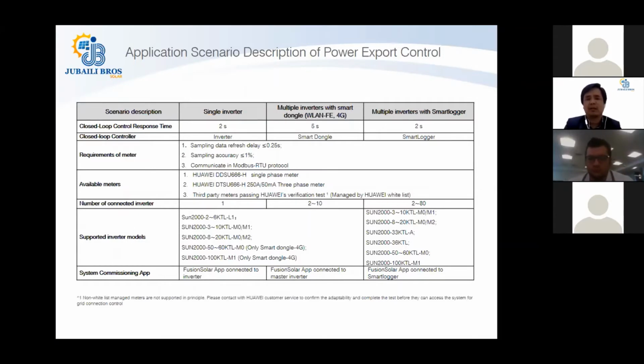That list is for the third-party power meters, but Huawei also has its own power meters: the DDSU, the single phase meter, and the DTSU, the three-phase meter. With the single phase, normally you would need it for residential spaces where you are using our 2 to 5 kilowatt inverter. You still need zero export control, so that is an option to use. With the three-phase inverter, you have the option of using one or more inverters. It can be a small residential, or a small to medium-sized commercial project up to 170 kilowatt. You can use our DTSU power meter, which comes with CTs inside the power meter package. Apart from that, as I said, there are third-party meters listed with Huawei, which are already in the Huawei smart logger library as well. So there are different cases, as I said, with the single phase, single inverter. You have an option.